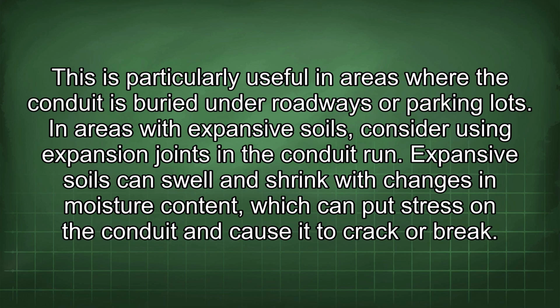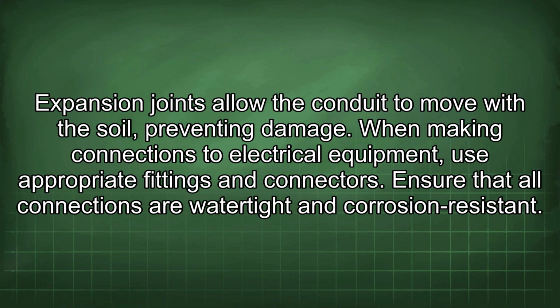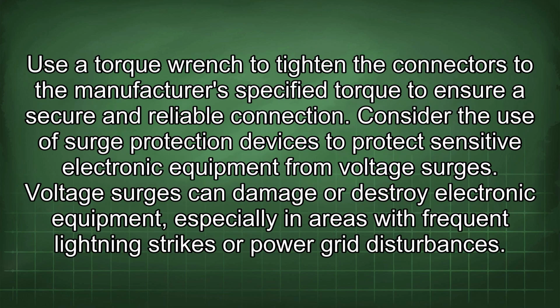In areas with expansive soils, consider using expansion joints in the conduit run. Expansive soils can swell and shrink with changes in moisture content, which can put stress on the conduit and cause it to crack or break. Expansion joints allow the conduit to move with the soil, preventing damage. When making connections to electrical equipment, use appropriate fittings and connectors. Ensure that all connections are watertight and corrosion resistant. Use a torque wrench to tighten the connectors to the manufacturer's specified torque to ensure a secure and reliable connection.